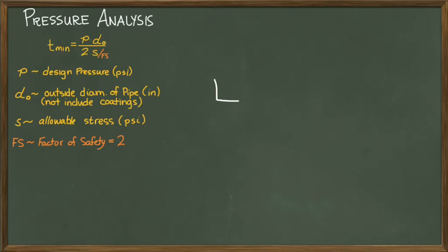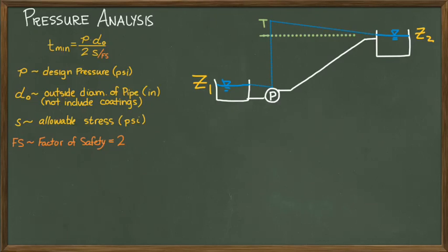Design pressure. If we look at this simple hydraulic schematic, you may initially think perhaps the design pressure is merely the hydrostatic head shown here as the difference between Z2 and Z1. But then you would quickly correct yourself because this is only true when the pump is off and the water is simply flowing down the hill.